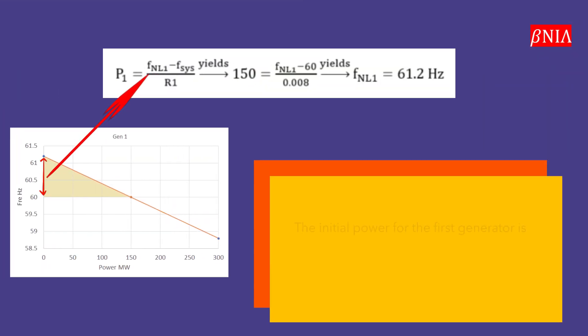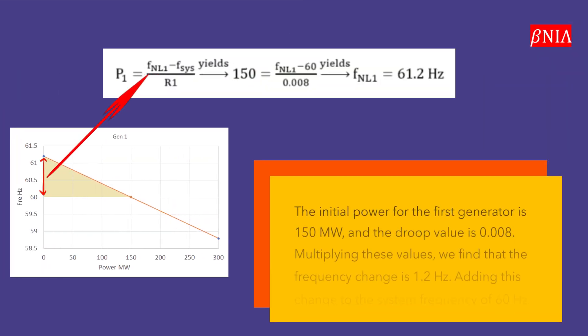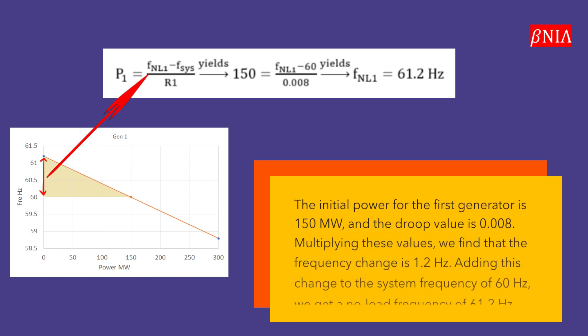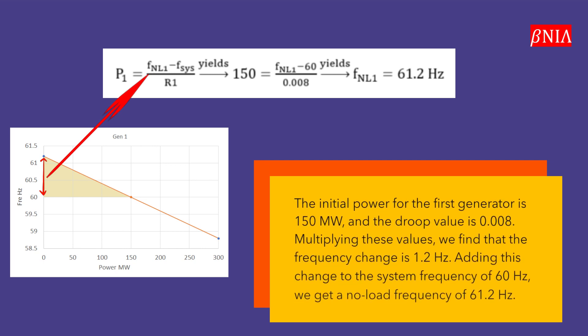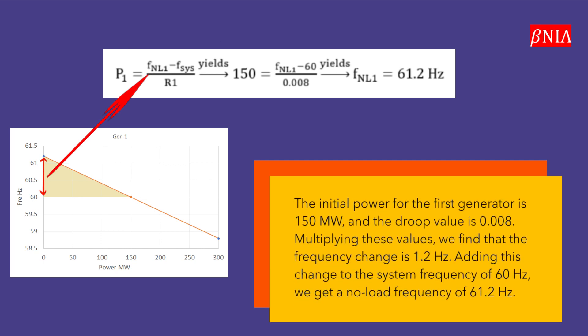The initial power for the first generator is 150 MW, and the droop value is 0.008. Multiplying these values, we find that the frequency change is 1.2 Hz. Adding this change to the system frequency of 60 Hz, we get a no-load frequency of 61.2 Hz.